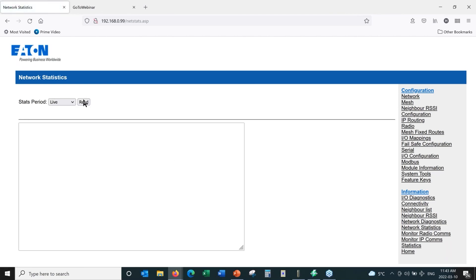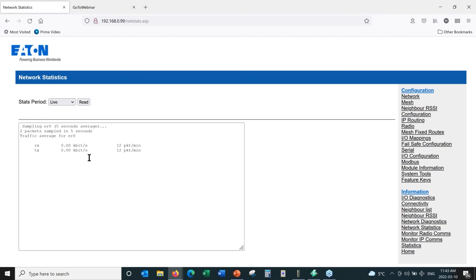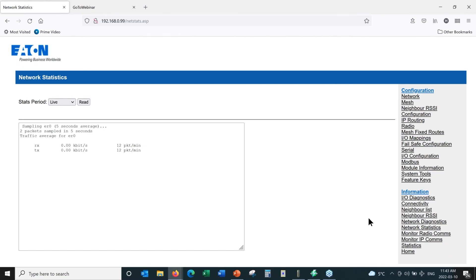Then we have network statistics. We hit Read and it gives us basic information about how many packets per minute are being sent over the radio network. This tells us whether the network is really busy or pretty slow. Right now we don't have much data going across. With 20 or 30 remote radios, we'd see much higher numbers. This gives an idea of whether we're overburdening the radio network with too much traffic, and shows the usage of the frequency channel we're using.